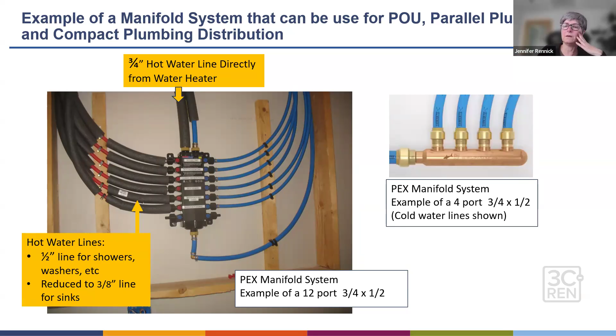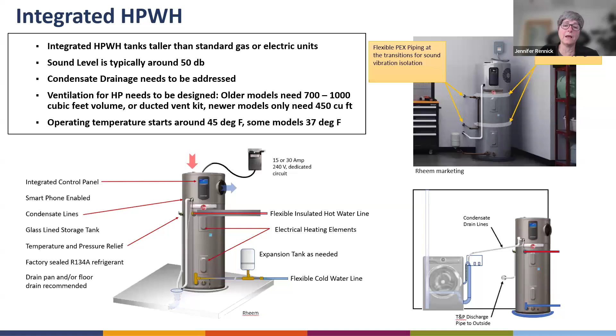For the integrated water heaters, I put this slide in here because there's things to know. This comes up on remodels a lot. Like, where should we locate it? How much space do we need? What else do I need to have for this? So especially on new construction too. I mean, it's just new for the heat pump water heaters. And so this is here as a reference to give you kind of a visual and a labeling of what all the parts and pieces are that are needed for heat pump water heaters. And as a designer, you want to have enough room for all of it.